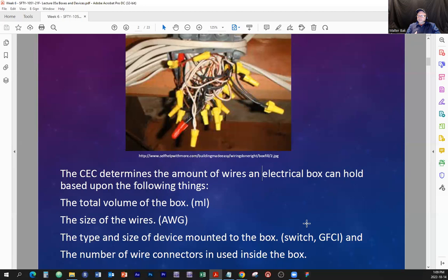Notice that this is ground fault circuit interrupt. So that would be the ground fault, right? That means the current that's flowing out is supplying the load and is also supplying the current that is flowing out of there, wherever it goes to the ground. And whatever comes back would be the current that's flowing in minus the current that escapes through the device box to the ground. So those currents will be different.